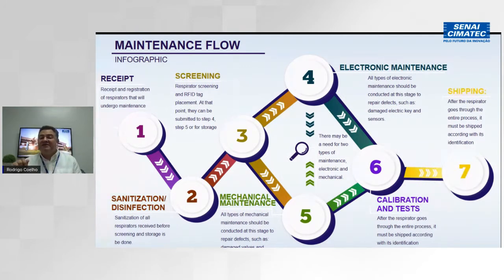And this starts with cycling the equipment, doing some tests with this equipment, where I can see by the alarms and by the noise and the signals of the equipment which kind of maintenance this equipment requires. So I can go for electronic maintenance and also for mechanical maintenance, and even both. Most of the time, I also need to change a kind of plug, mechanical interlock, fastening, that is just breaking down the tip. Maybe this is the case and I need to repair, or using some glue, or even some 3D printing with polymeric materials, where I can fix those mechanical parts in a proper way.